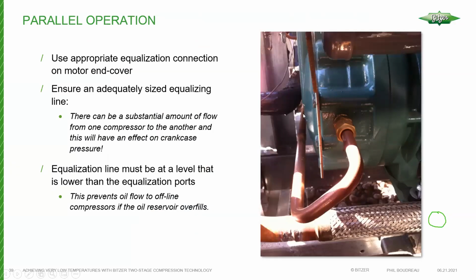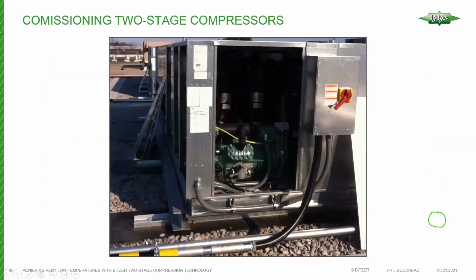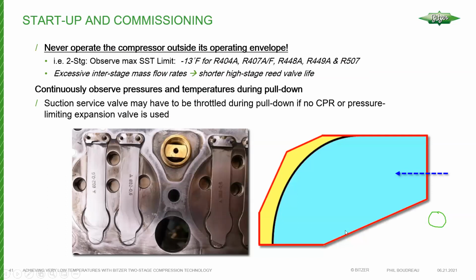When paralleling the compressors, we equalize them using another fitting in the back end of the motor housing. In this case, we'll use a fairly large equalizing line, equalize that pipe down low between the compressors, and then that check valve from the low pressure reservoir will be vented to this connection here. We don't have a lot of time left, so just a few quick notes.